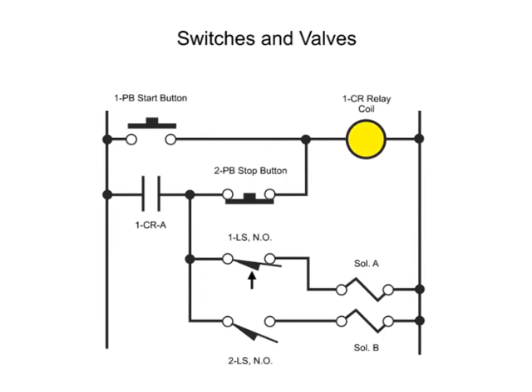Its coil is shown as a circle marked 1CR. Holding relays typically operate one or more relay contact sets. In this diagram, the holding relay operates one set of contacts. The contacts are depicted as normally open. As with switches, they can also be manufactured as normally closed, with a slash mark depicting the normally closed state.